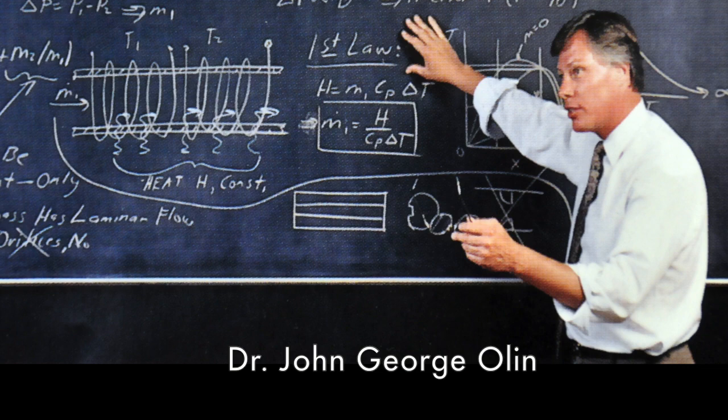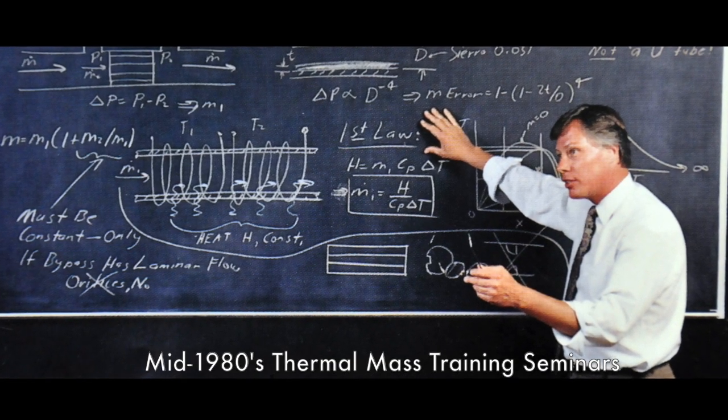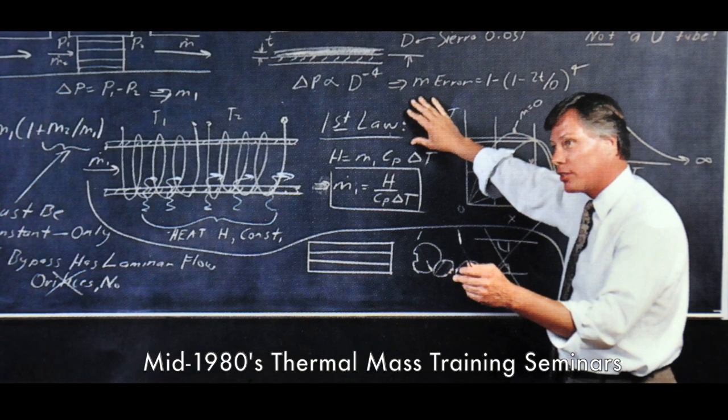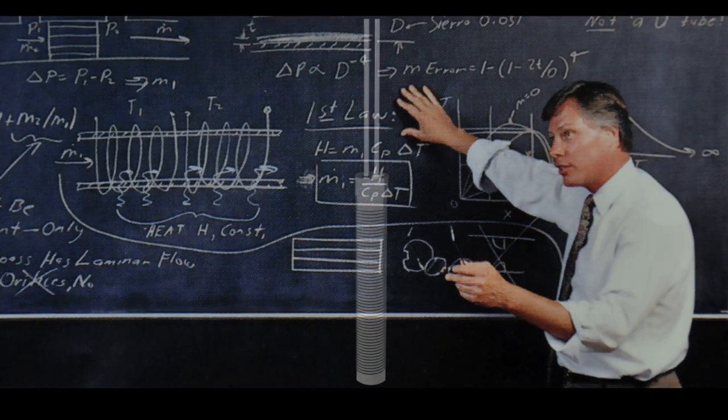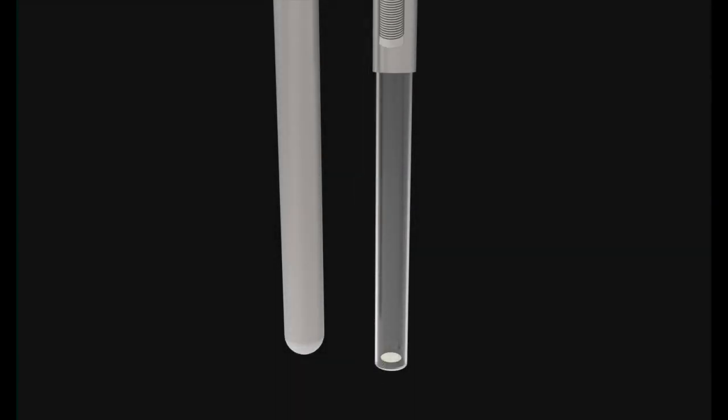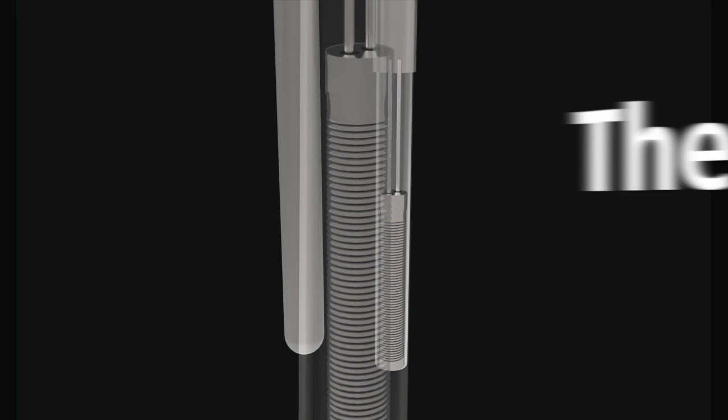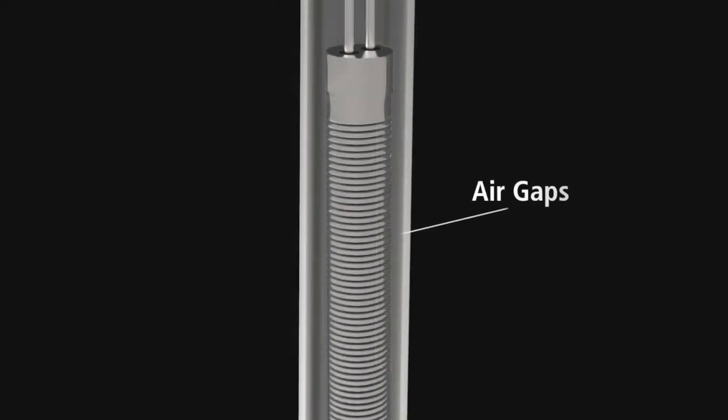To make a thermal flow sensor truly industrial strength, Dr. Olin pioneered the innovation of an all-metal clad thermal sensor in the early 1980s, winding platinum wire around a ceramic mandrel and placing it inside a metal sheath called a thermowell. The problem was that the air gaps between the thermowell and the platinum wound mandrel needed to be filled to assure stable heat transfer. This was the key to assuring an accurate and stable thermal mass flow meter.